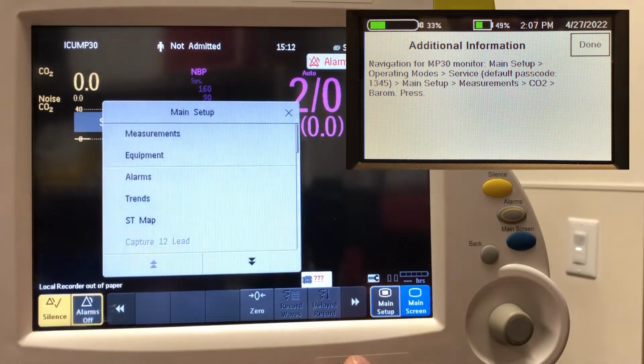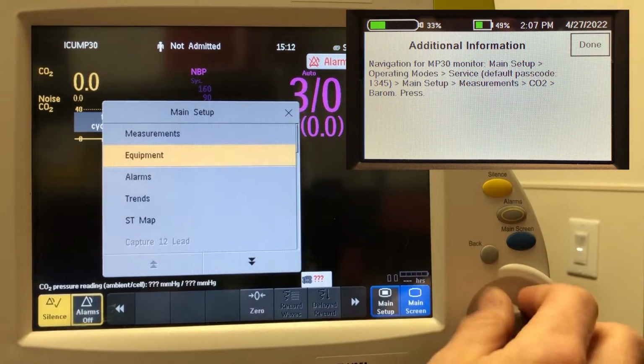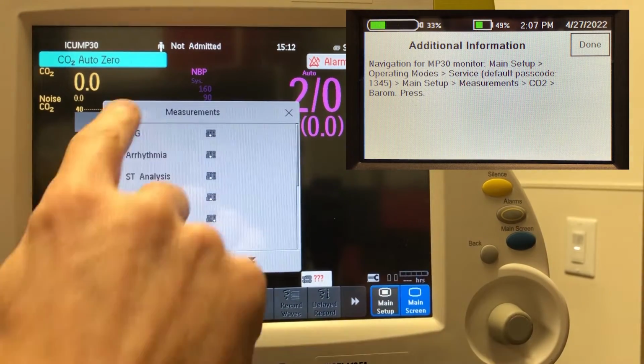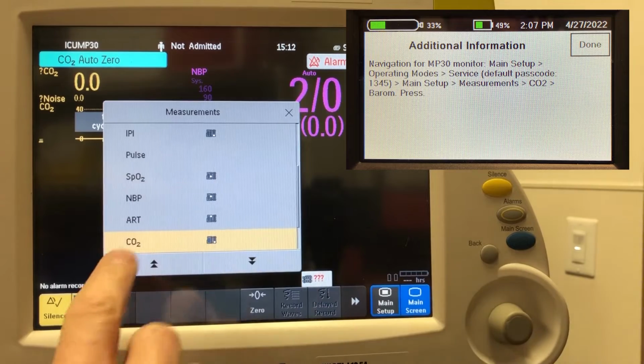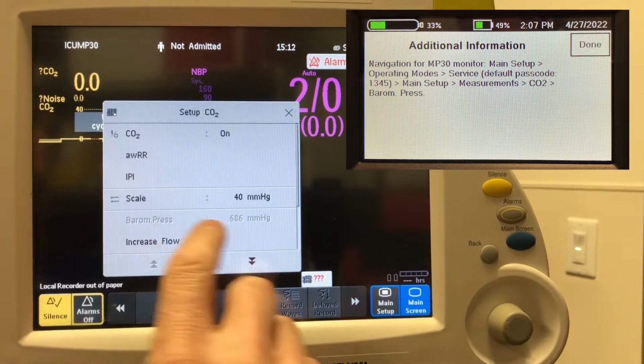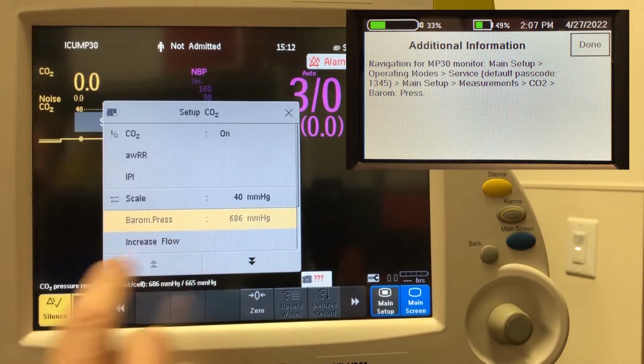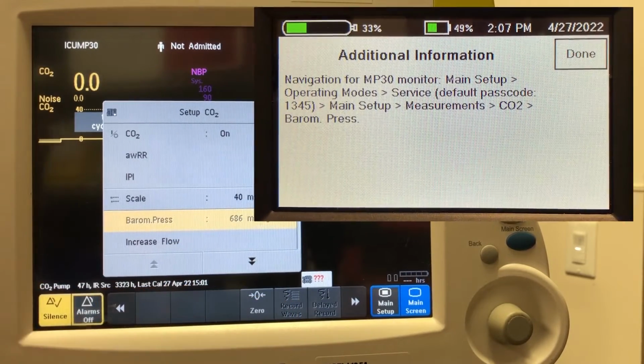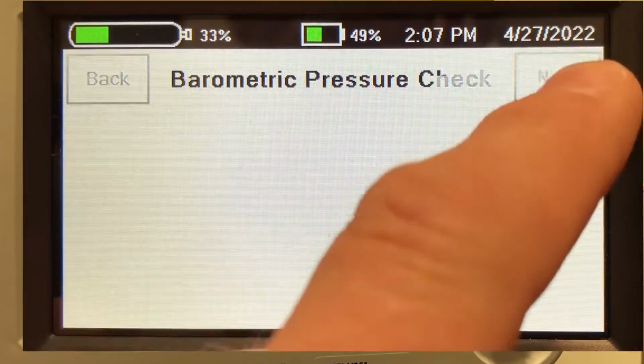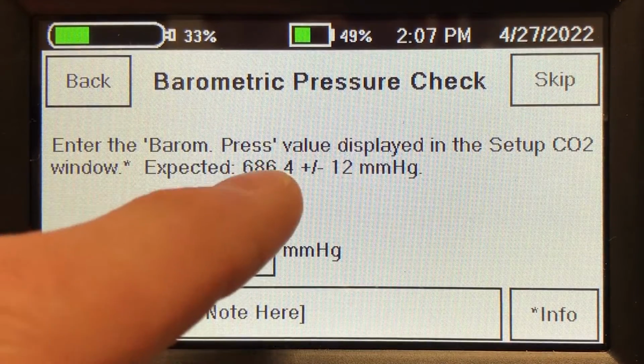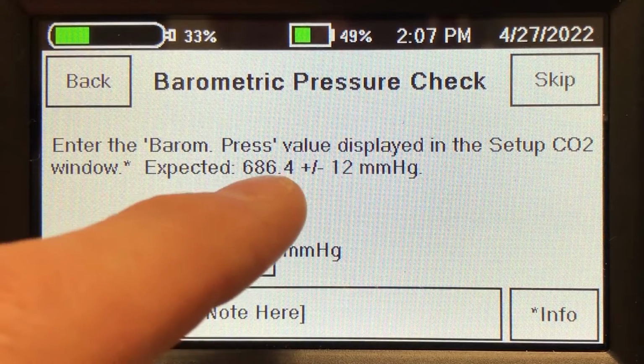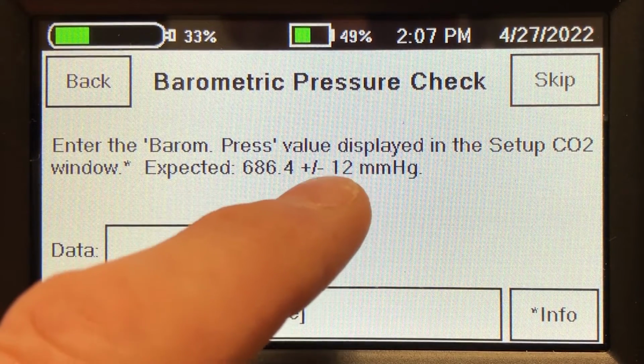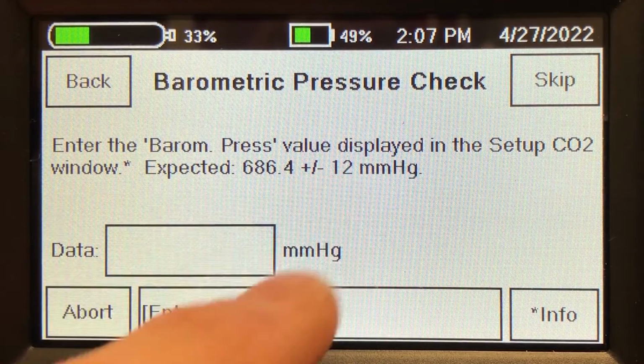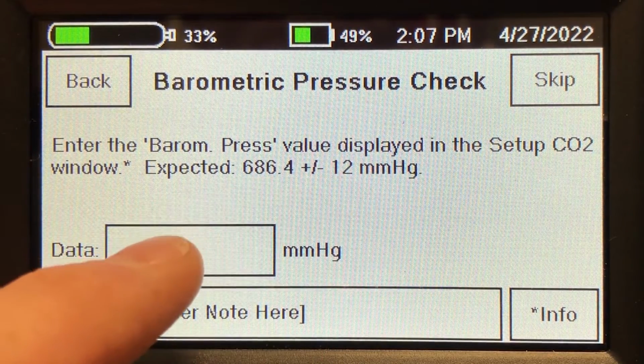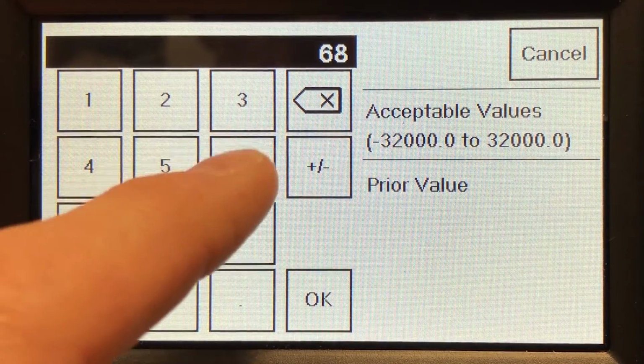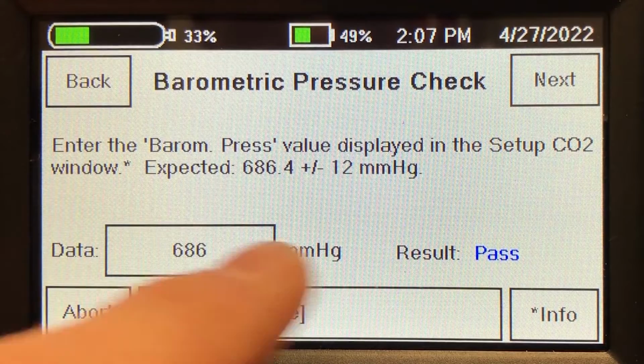Now we go back to main setup and select measurements. Now we'll scroll down to CO2, and here we can see the barometric pressure is read right there, 686. It also reads it right here in this scrolling message at the bottom. So we hit done there. I'm going to move to the next screen. So here 686.4 is the reading from the barometer inside the smart tank, and the plus or minus 12 is the pass criteria for this device. So you can see that this device is actually reading almost exactly perfect barometric pressure. So that's a passing result.